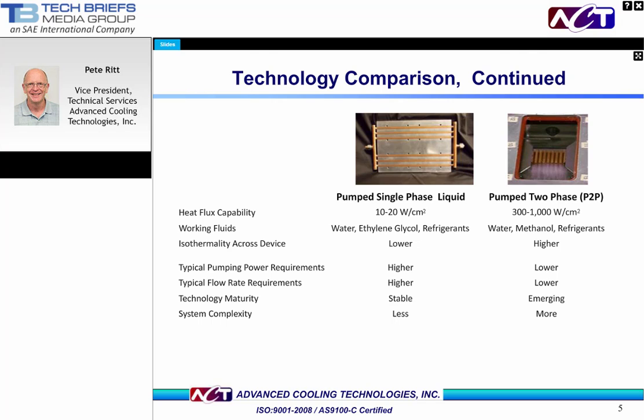Here is a chart that compares and contrasts key attributes of pump single versus pump two-phase cooling, which are the two most common thermal management technologies used to dissipate kilowatt or higher heat loads. In terms of heat flux capability, pump two-phase has a significantly higher capability, with pump liquid systems typically in the 10 to 20 watt per centimeter squared range, and pump two-phase from 300 up to even 1,000 watts per centimeter squared.